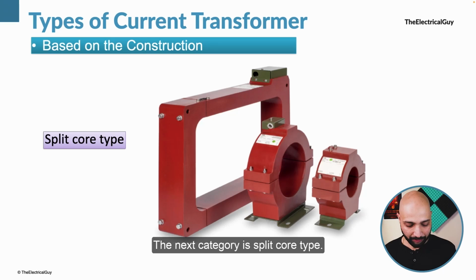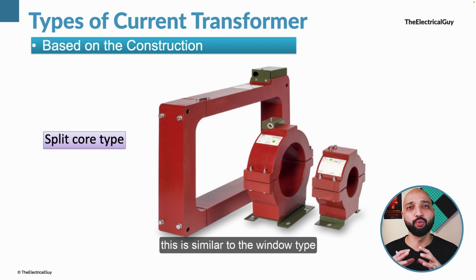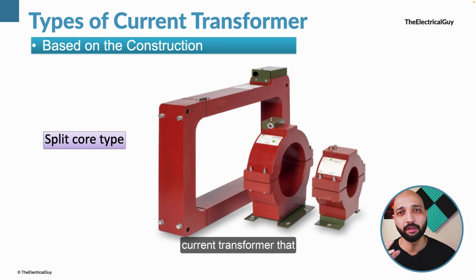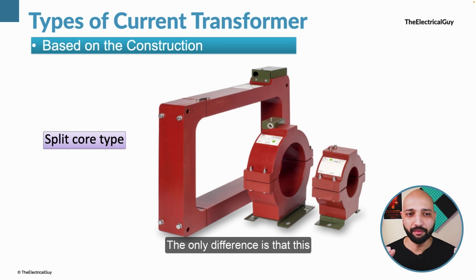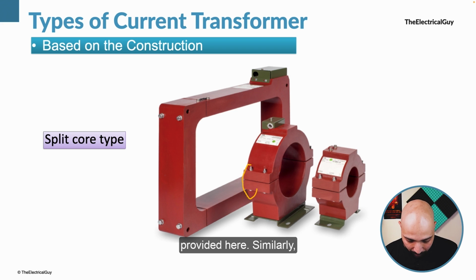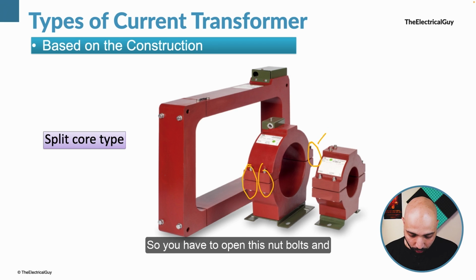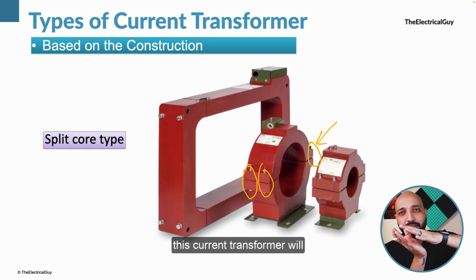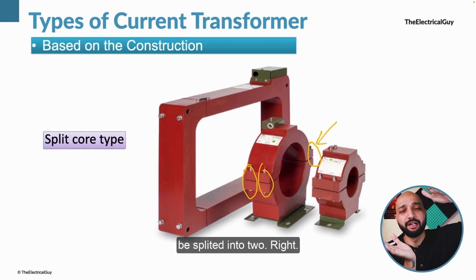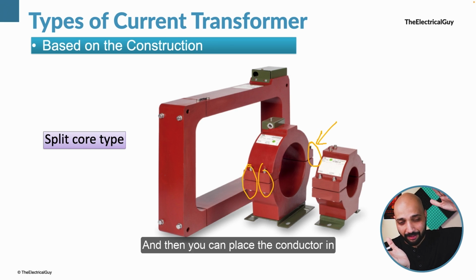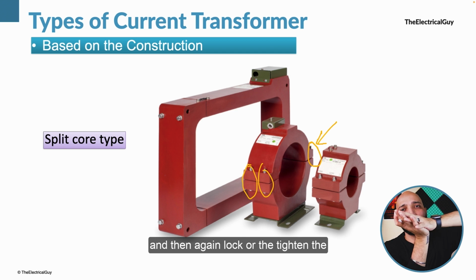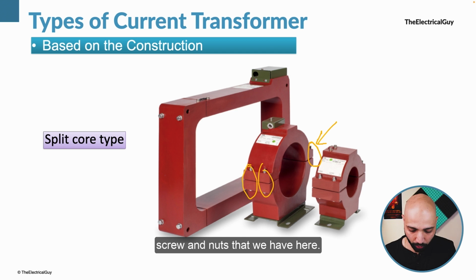Now moving on, the next category is split core type. This is similar to the window type current transformer that we just discussed. The only difference is that this current transformer can split. You can see there are nut bolts provided here. Similarly, from the other side also there will be nut bolts. So you have to open these nut bolts and this current transformer will be split into two, right? And then you can place the conductor in and then again tighten the screws and nuts that we have here.